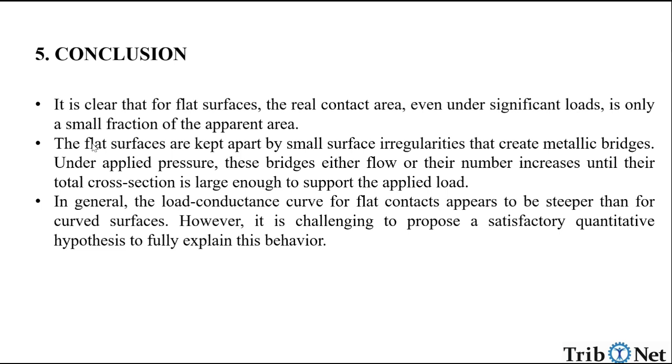So finally, what are the conclusions from these findings? It is clear that for flat surfaces, the real contact area, even under significant loads, is only a small fraction of the apparent area. The flat surfaces are kept apart by small surface irregularities that create metallic bridges under applied pressure. These bridges either flow or their number increases until their total cross section is large enough to support the applied load. In general, the load conductance curve for flat contact surfaces is steeper than for the curved surfaces. However, it is challenging to propose a satisfactory quantitative hypothesis to fully explain this behavior.